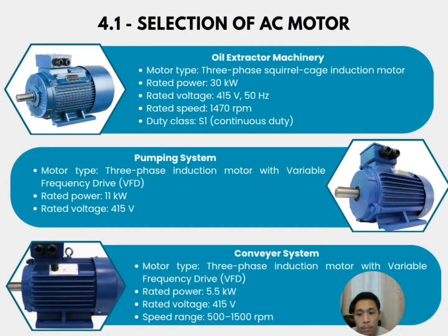Next is our pumping system. While this also uses a 3-phase induction motor, we have integrated a variable frequency drive, known as VFD. For the power, this is an 11 kilowatt motor operating at 415 volts. The advantage of using a VFD is that we can control the motor speed to match the fluid flow requirements. This significantly reduces energy consumption and prevents water hammer effects in the pipes by allowing for smooth starts and stops.